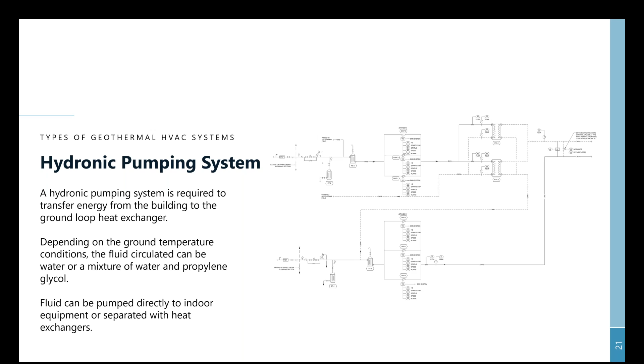So let's talk about the equipment that gets placed inside of a building that is paired with the ground loop heat exchanger. One approach is to look at more centralized HVAC equipment. When we say centralized, that would be like the image in the top left corner, basically a ground source heat pump air handling unit. They can be large scale air handling units, VAV air handling units. So the distribution within the building may be very similar to VAV distribution that a lot of people have seen in commercial office buildings and other types of applications. The difference is that it's not a chilled water, hot water system with a cooling tower and a boiler. We're using the ground source loop directly to transfer energy.